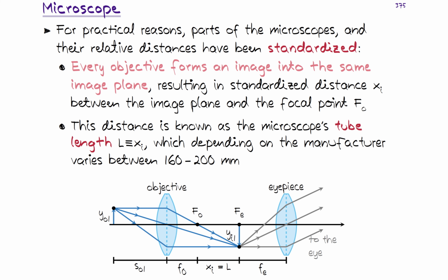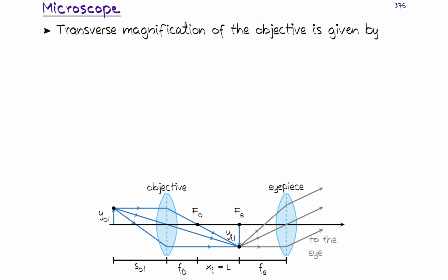And for some vendors, it's 200 millimeters. So this is good to keep in mind: if you need to buy an objective lens, please look at what kind of objective lenses you already have, so that you don't accidentally buy a wrong one where the tube length is not the same, because then you start having trouble. Of course, there are adapters, but nevertheless, my recommendation is that you just keep on buying products from the same company, unfortunately as it is.